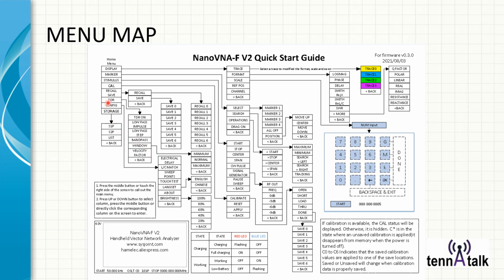The next thing I would do is set my display. And from there, I've got the traces. I've got 4 traces, 0 through 3, of these 4 colors that it comes up with, and you can activate them or deactivate them. The format of each trace, whichever one you've selected and highlighted, there'll be a little checkbox over here, will be the one that the format will apply to. You can set it up to SWR for trace 0 in yellow, and Smith with R plus jX reactance for green. That's pretty common. That's very often the default.